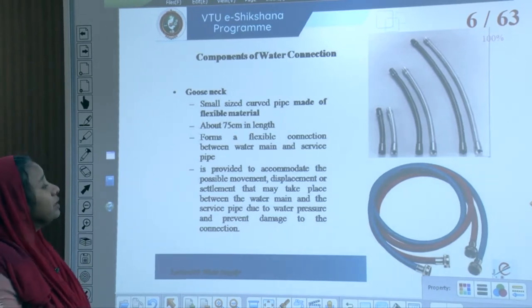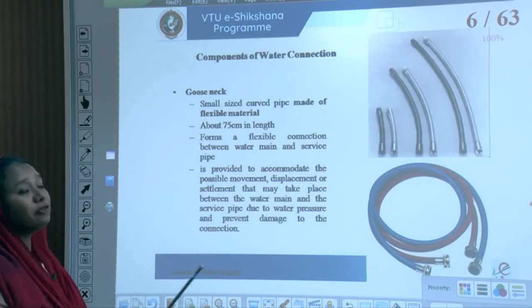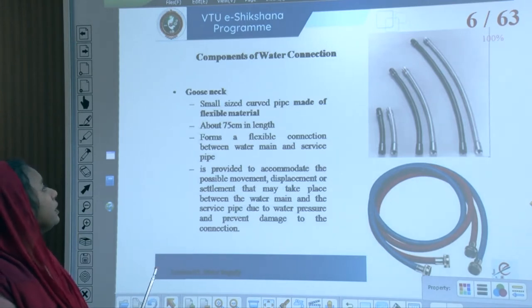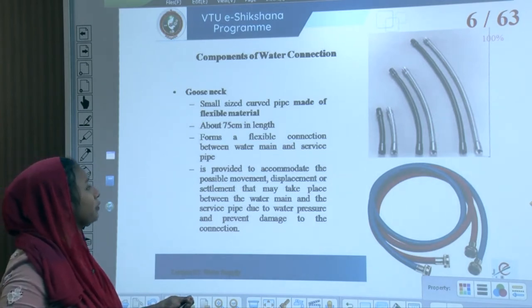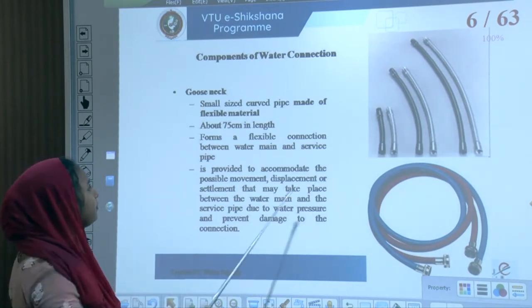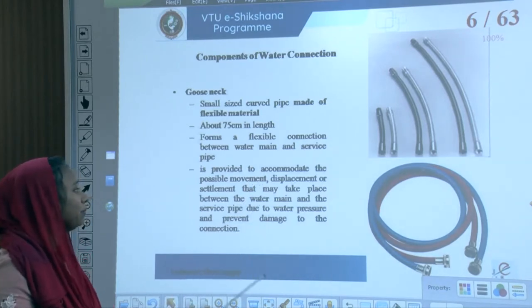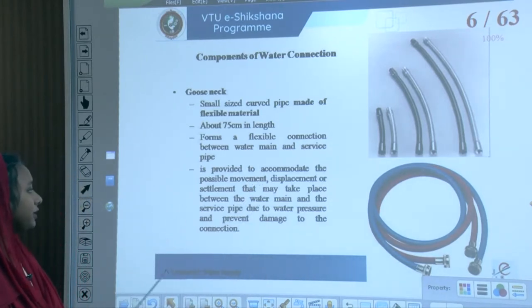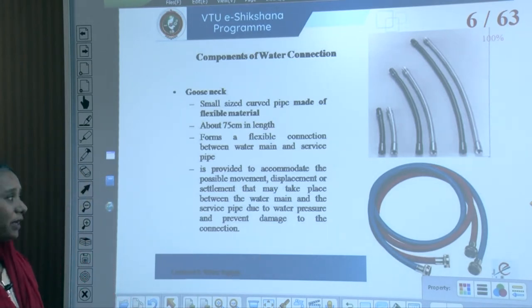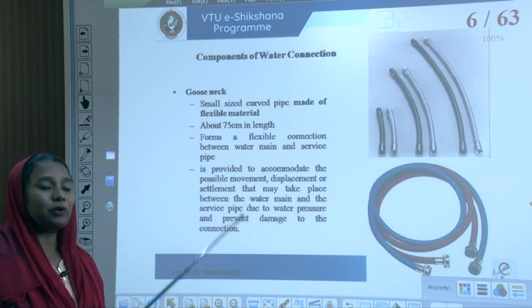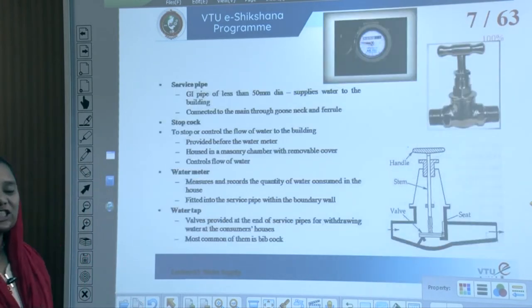A gooseneck is a small curved pipe made of flexible material, about 75 centimetres in length, forming a flexible connection between the water main and the service pipeline. It accommodates possible movement due to displacement or settlement between the water pipeline and service pipeline, caused by water pressure, and prevents damage to the connection system.